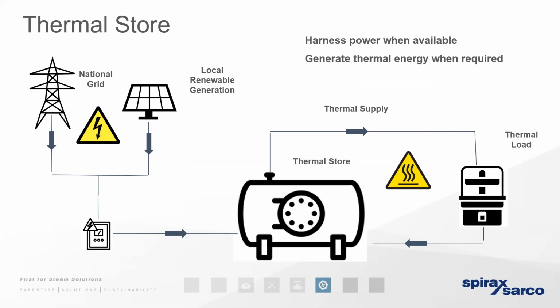So we can use the electrical energy, the power, either from the grid or from renewable sources, and we can use that to charge a mass of water under pressure. In other words, we're bringing that water up to temperature whilst it's under pressure, so it's still in a liquid phase. If you remember the basics of the steam fundamentals that we looked at earlier in the slide, well, if we depressurize that hot water, we're going to get flash steam being produced. And remember, there's just as much energy in flash steam as there is in plant steam. So we can use that flash steam in exactly the same way that we would use the plant steam on a traditional system to satisfy the demand by the process.